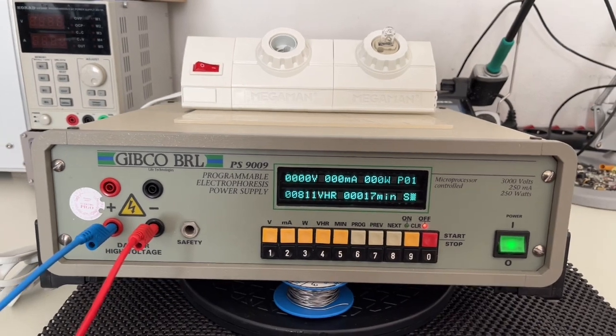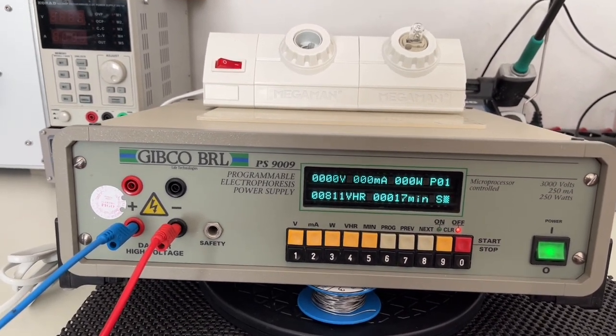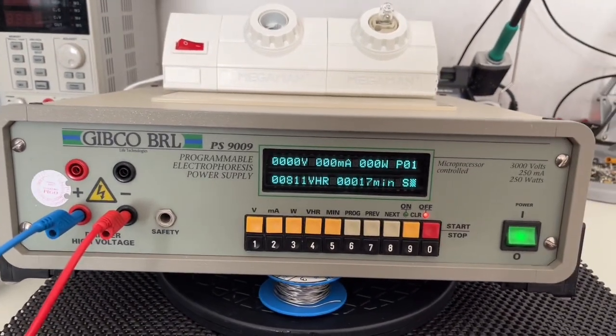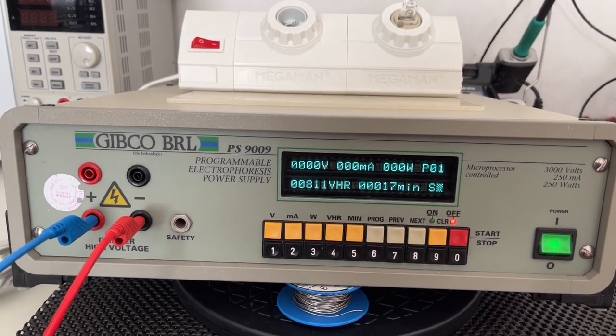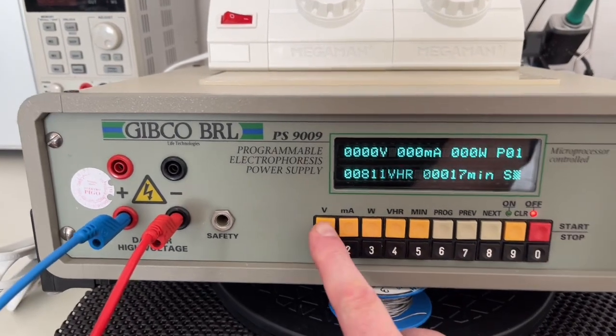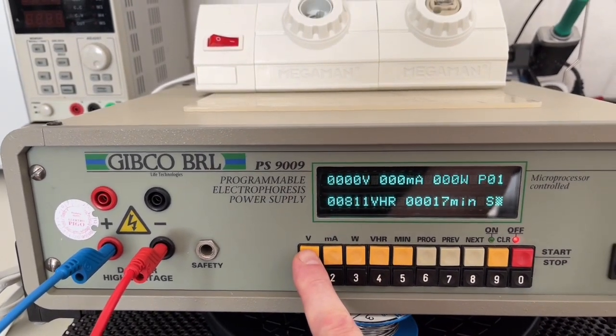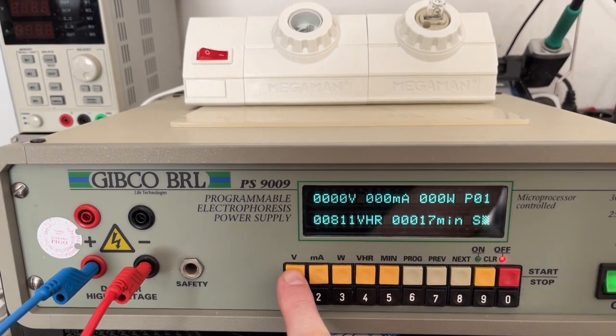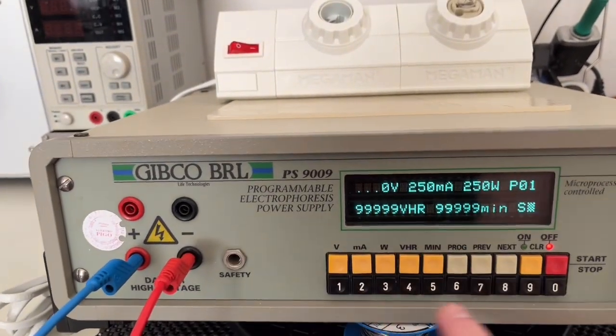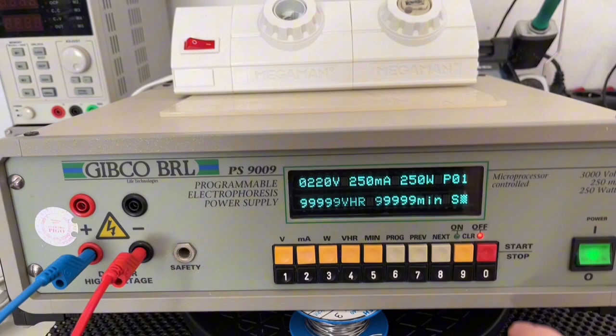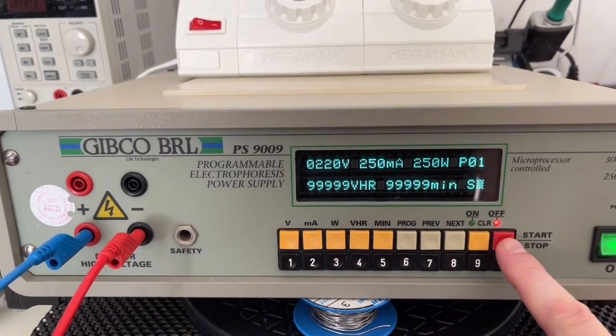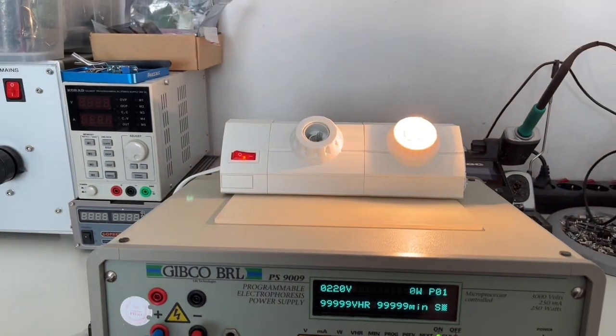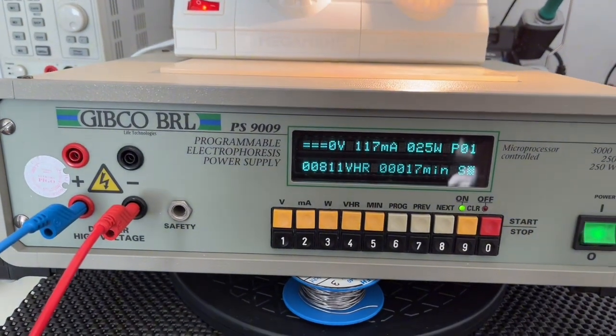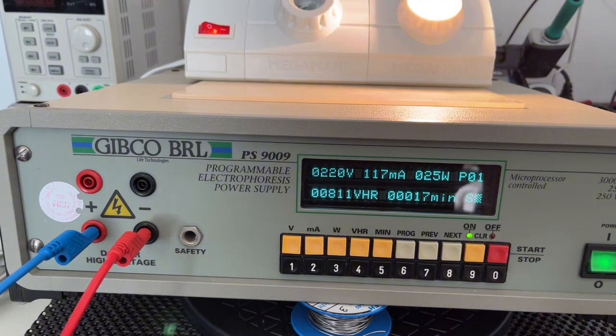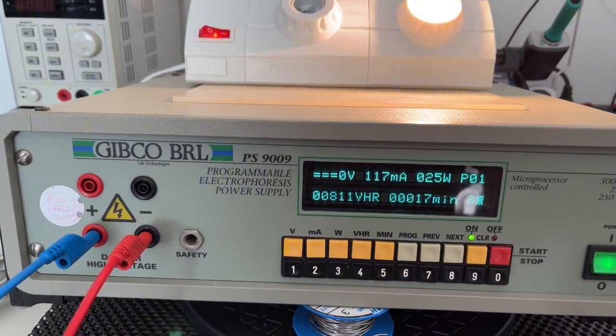You have program places, I think we have 99 programmable voltages to use. It is quite easy to set the voltage, the current and the power. For the voltage you press volts, and let's say 220 volts, you have to put 0 2 2 0. Same with milliamperes and watts, and then you press the start stop button and it should output something. You see, it's already outputting 220 volts, and the lamp I'm using is a 25 watt lamp and draws 117 milliamps.